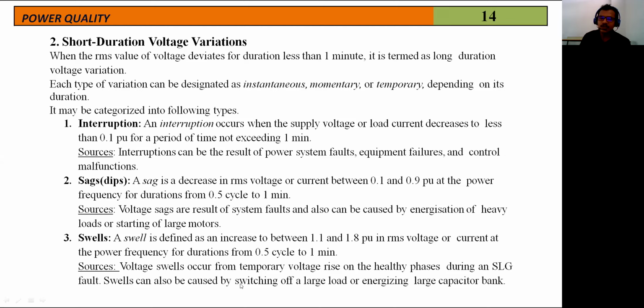Swells can also be caused by switching off a large load or energization of a large capacitor bank. Suddenly switching off a large load, or suddenly switching on a large capacitor bank, will increase the voltage or make a voltage swell. So these are short duration voltage variations.